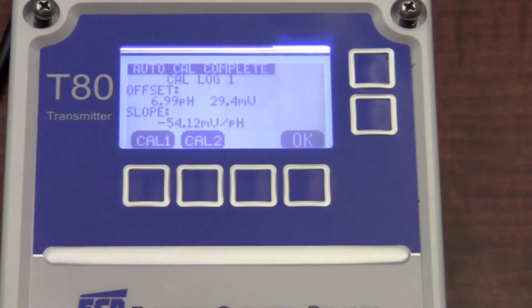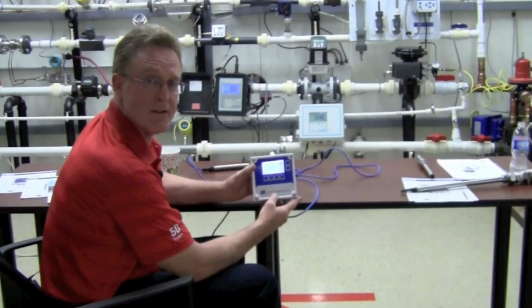The screen does give me an approximate slope as well. As you can see, mine is 54.12 millivolts. 7 pH shows you approximately 0 millivolts. You would get an offset with degradation over time of the reference half cell that's exposed to the process. In our particular case, we see that we still have an acceptable slope of 54.12. That's acceptable up to approximately 50 millivolts.